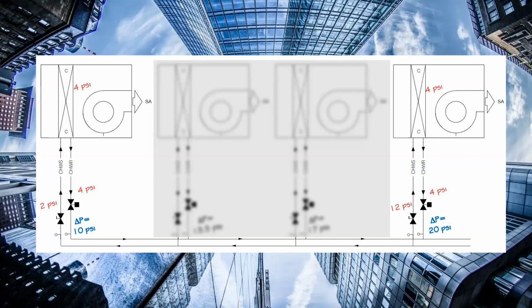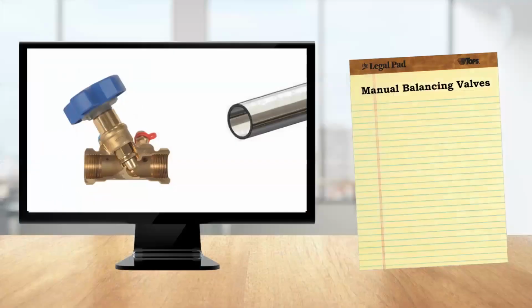So in order to understand potential troubles, we need to understand how balancing valves work, right? I'm sure many of you, if not all of you, understand this already, but we'll go through it anyway. A manual balancing valve works like this: if the valve is fully open, there's 100% flow, balancing condition, there's no pressure drop or a very small one. The pipe represents an unrestricted flow area. Note the 100% flow, no pressure drop while the balance valve is fully open.